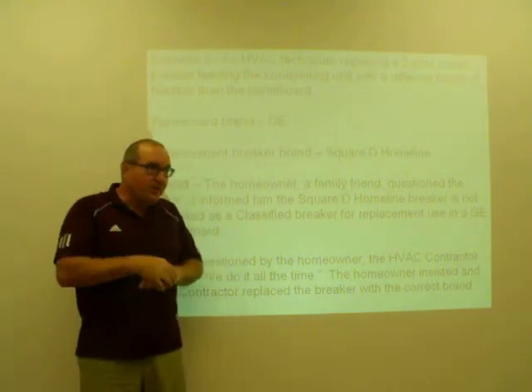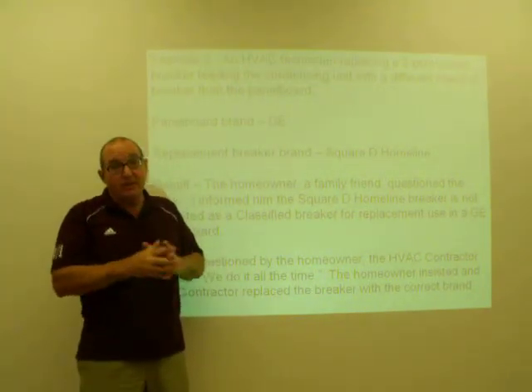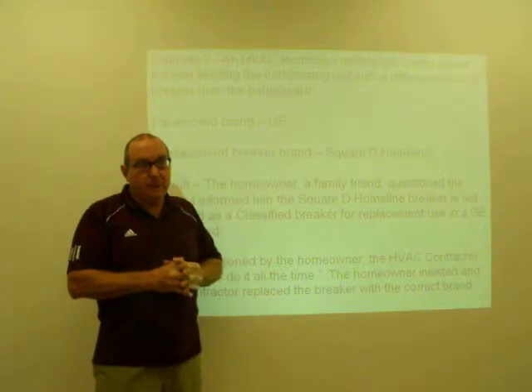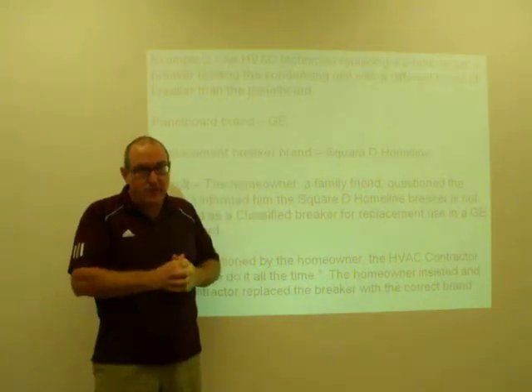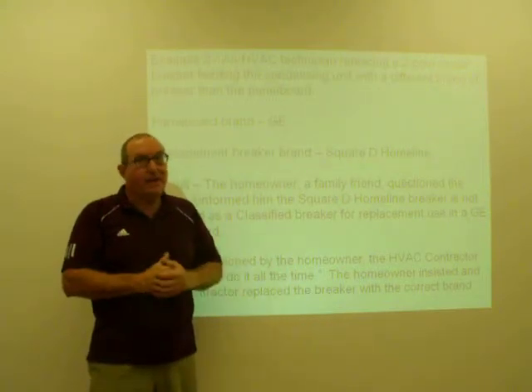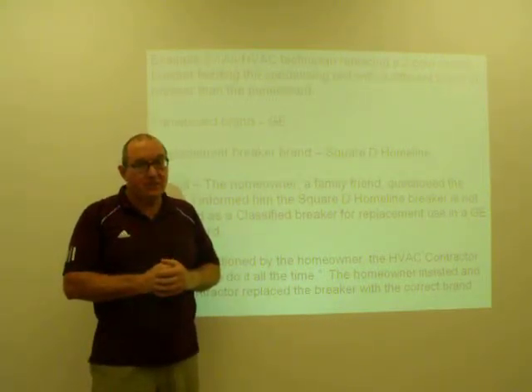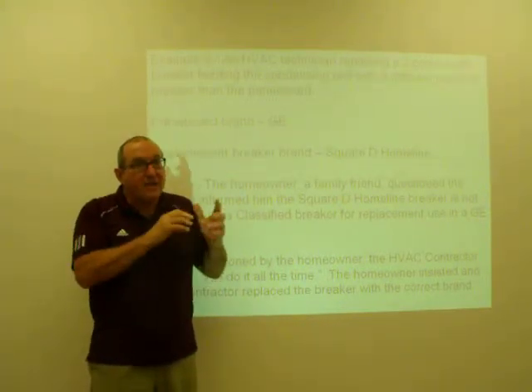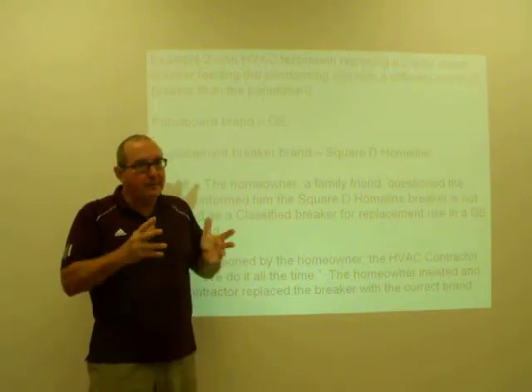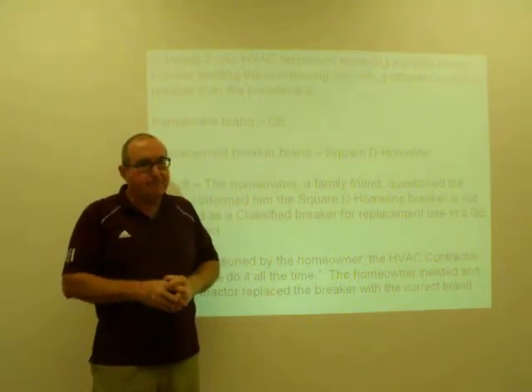I'll go into some examples here of some of the breakers he tried to use later. I will tell you at one point when I was demonstrating the deficiencies to the owner, I touched a breaker and it fell out of my hand. So that gives you an example of how that non-GE breaker would fit in the panel, but really didn't fit.